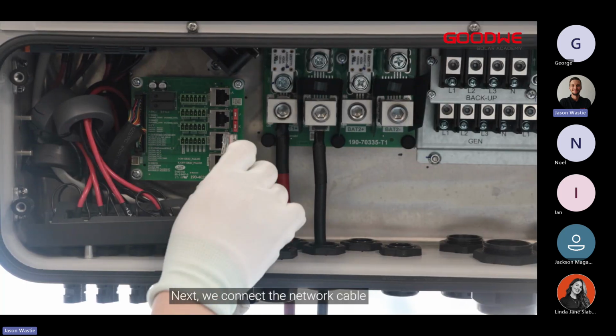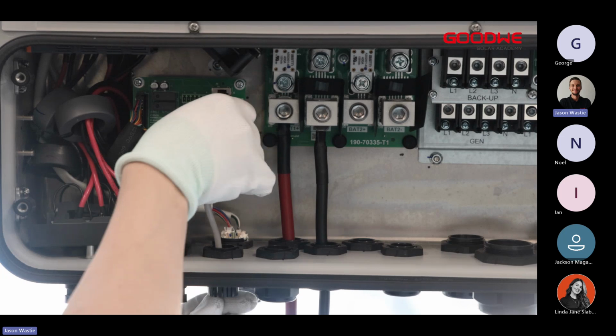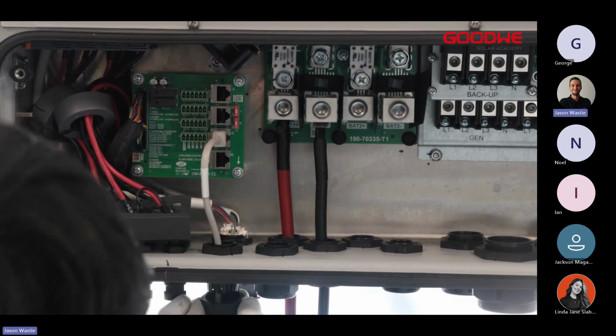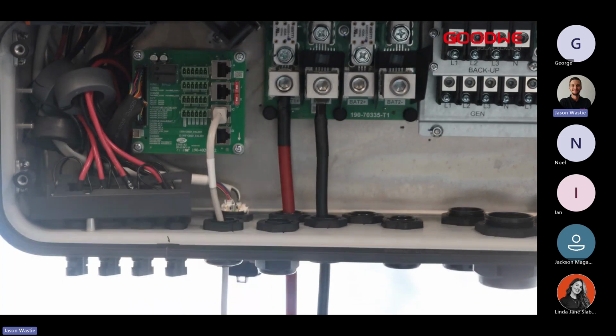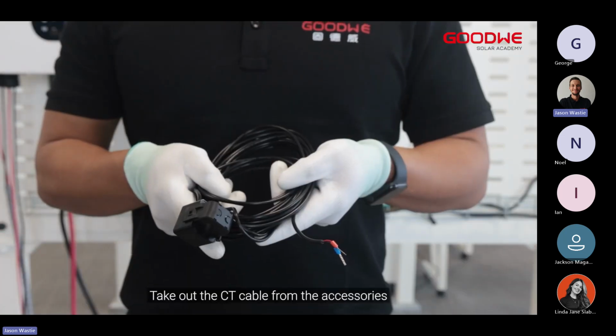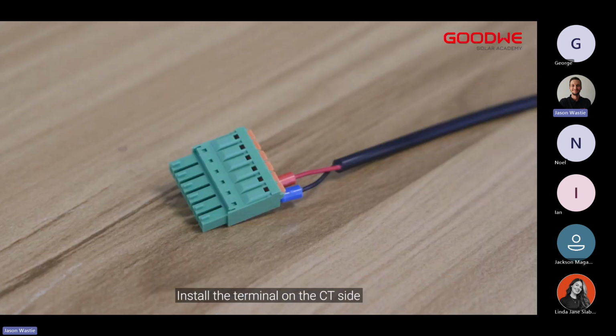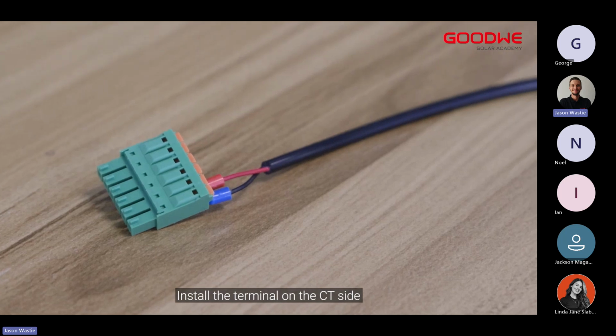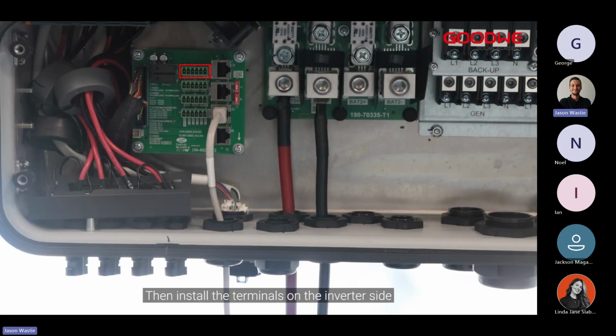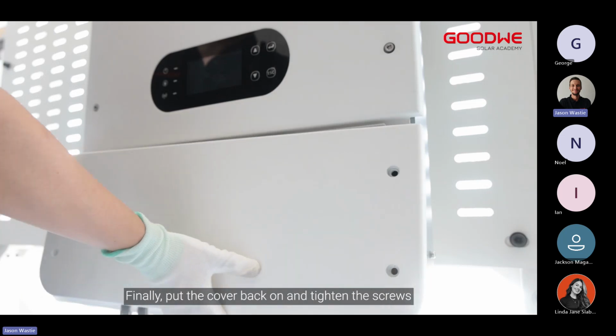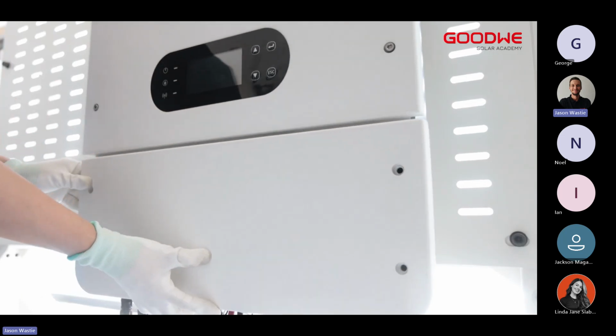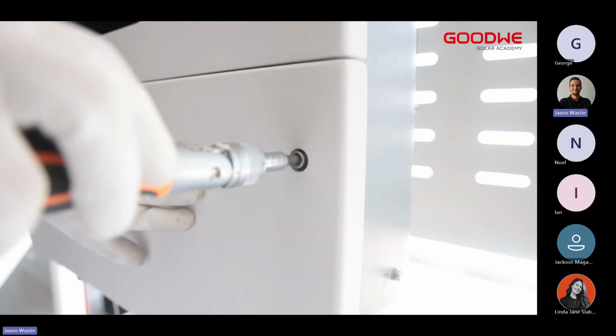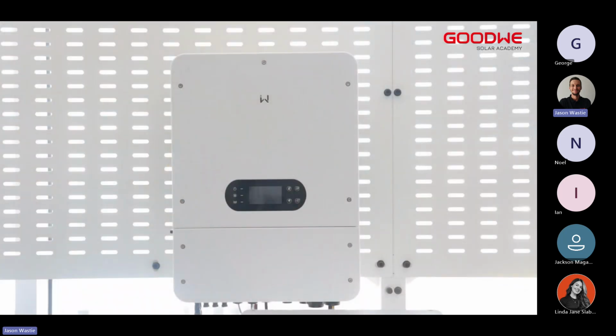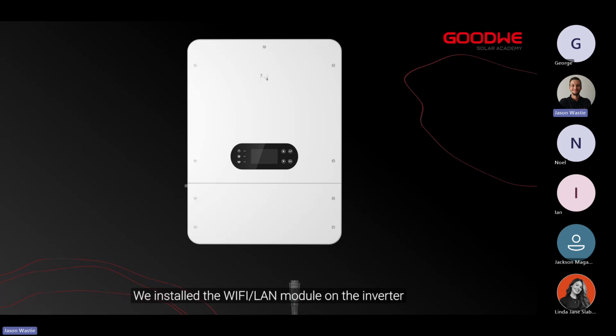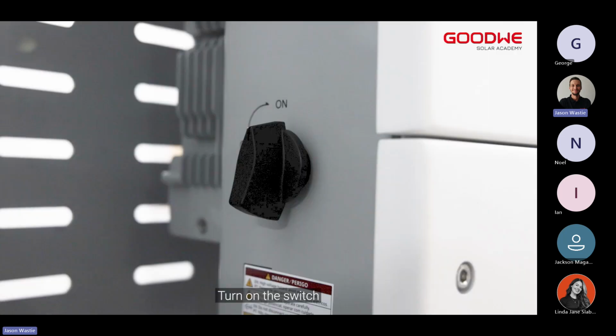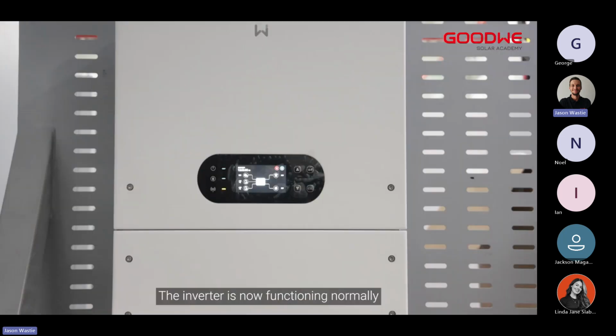Next, we connect the network cable. Take out the CT cable from the accessories. Take out the 6-pin terminal. Install the terminal on the CT side. Then install the terminals on the inverter side. Finally, put the cover back on and tighten the screws. We installed the Wi-Fi LAN module on the inverter. Turn on the switch. The inverter is now functioning normally.